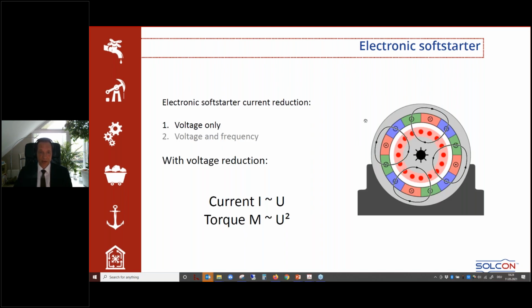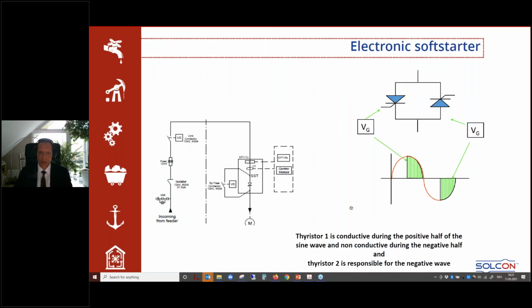Coming now to electronic soft starting. Here you have two possibilities. You can reduce the voltage only, or you can reduce voltage and frequency, to which I come later. If we are reducing the voltage, then you know the current will be approximately proportional to the voltage. So 80% voltage means approximately 80% current, and the power rating is always proportional to current times voltage. That means the torque is proportional to the square of the voltage. That means reducing the voltage to 80% gives you a proportional torque of approximately 64%. This is important to know. So how does an electronic soft starter work? What you have here is, let's say, an example.